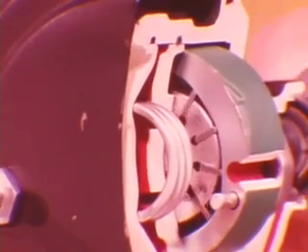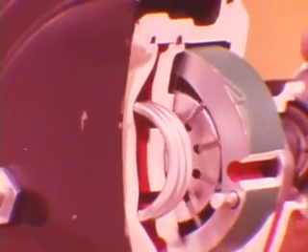A pulley-driven shaft drives a rotor with movable vanes. The vanes are pushed outward by centrifugal and hydraulic force and follow along the inside of a cam, which is wide at first, then narrows to a very small area.